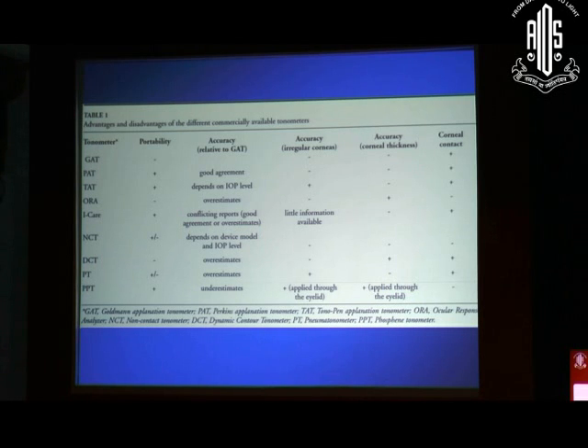It is affected by central corneal thickness. And while it does not make corneal contact and is therefore often touted as a very safe technique, you must remember that a jet of air can cause aerosolization of the NCT tears. If somebody has a potential infection, these infected tears can sit on the air jet, and the next patient can theoretically have a risk of infection. There have been reports of transmission of infection with this tool, so it needs to be cleaned occasionally, though not as rigorously as the Goldmann Applanation Tonometer.